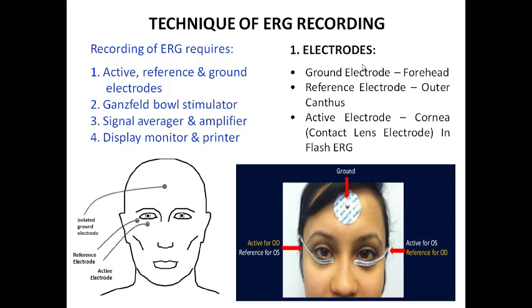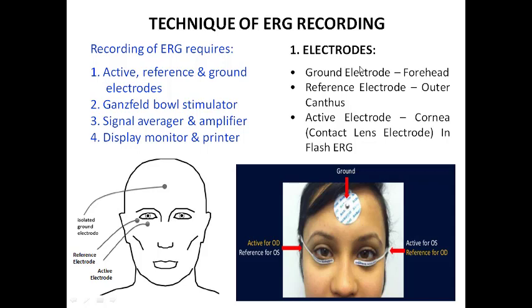For recording of ERG, we need electrodes. There are three types: active electrode, reference electrode, and ground electrode. The second requirement is a Ganzfeld bowl stimulator. The third requirement is a signal averager and amplifier. The fourth requirement is a display monitor or printer.